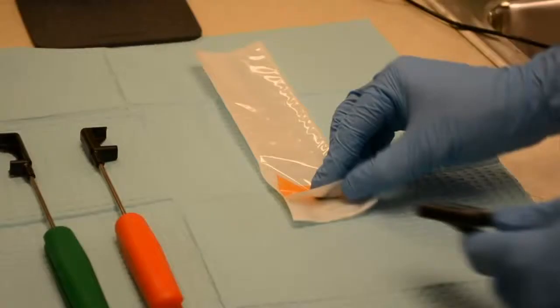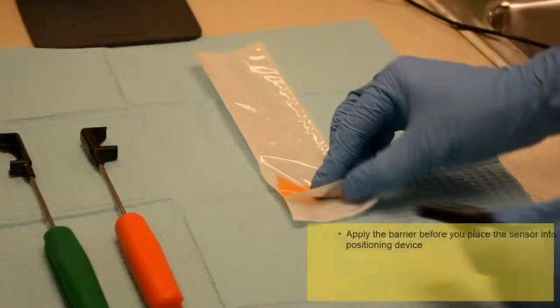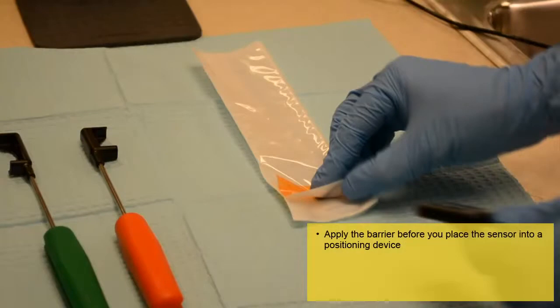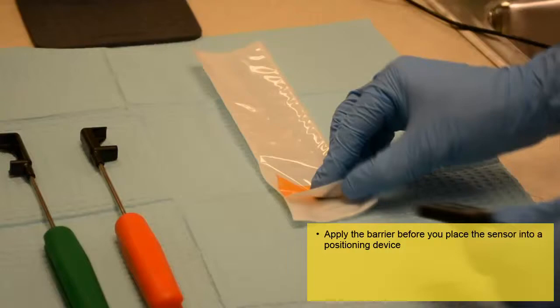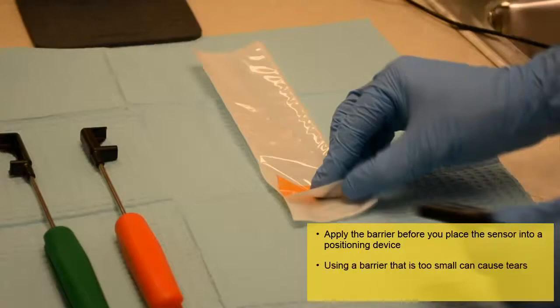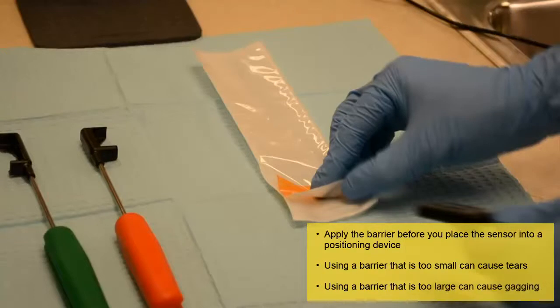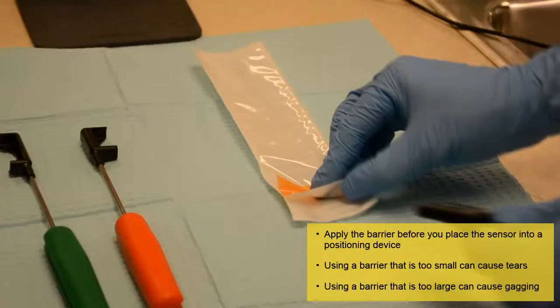You must cover the sensor with a barrier prior to use. Apply the barrier before you place the sensor into a positioning device. If you need to change positioners during use, you do not have to reapply a barrier. To begin, select the appropriate barrier. Using a barrier that is too small could cause tears, which can contaminate the sensor. Using a barrier that is too large can cause discomfort to the patient and can trigger a gag reflex upon placement.